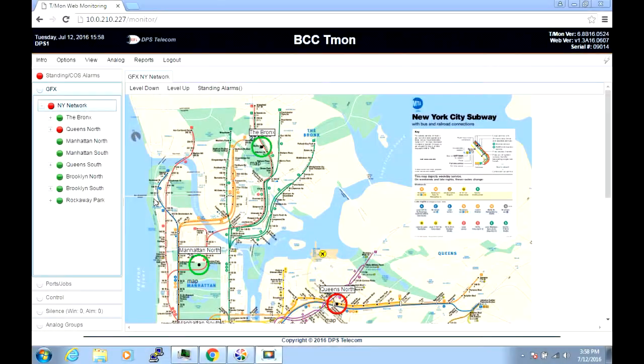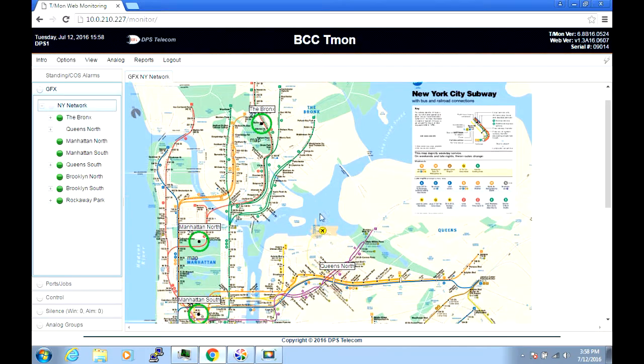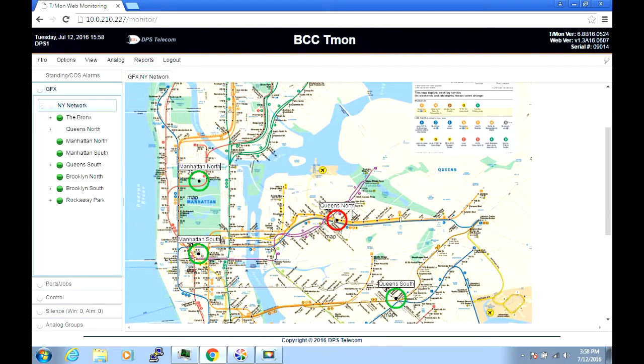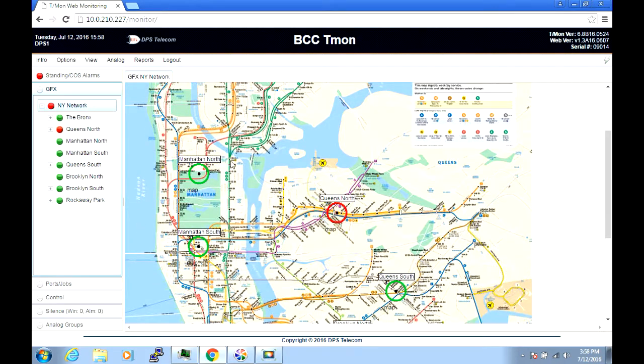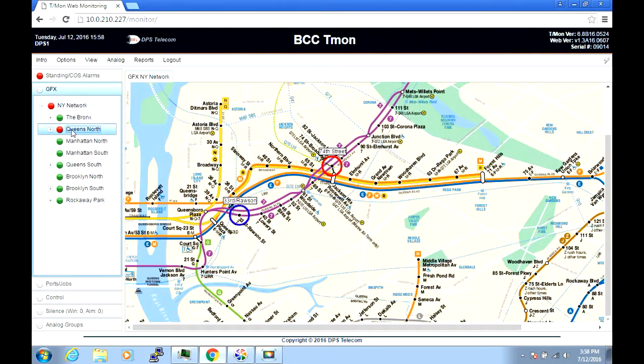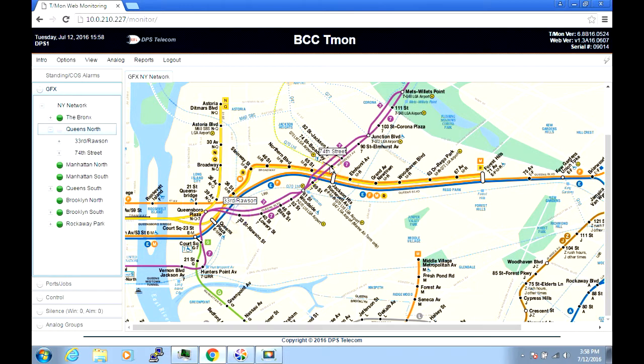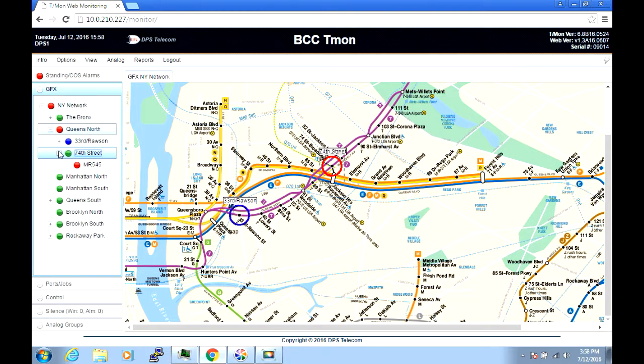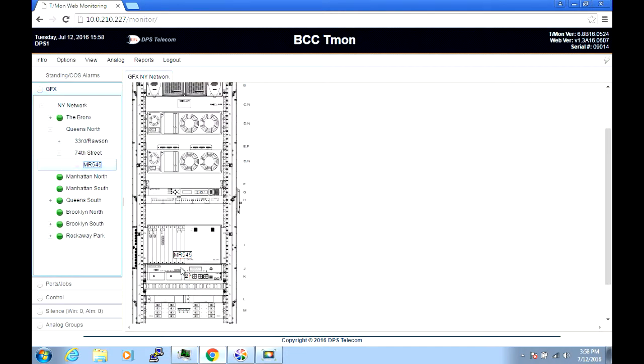When an event occurs, the indicator ring on the icon, or its higher level summary icon as shown here, will begin flashing to indicate that an unacknowledged change of state should be handled. Selecting the icon either displays a lower level or the COS list view if you're already on the lowest level.